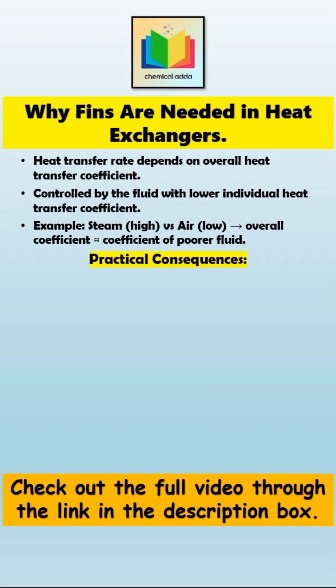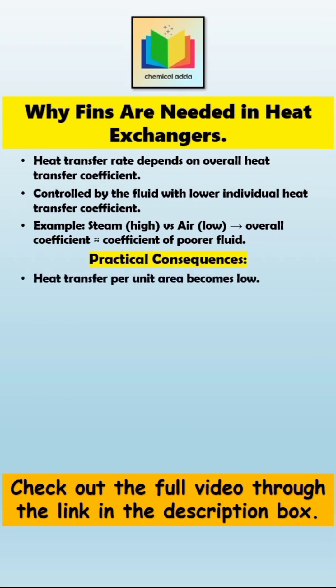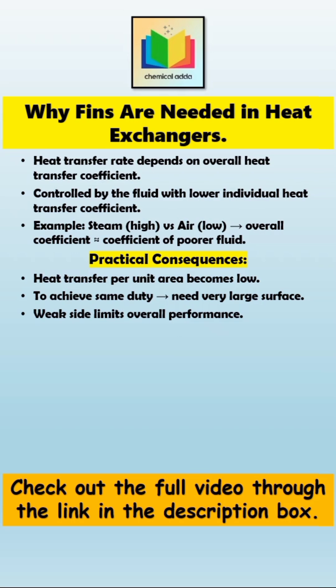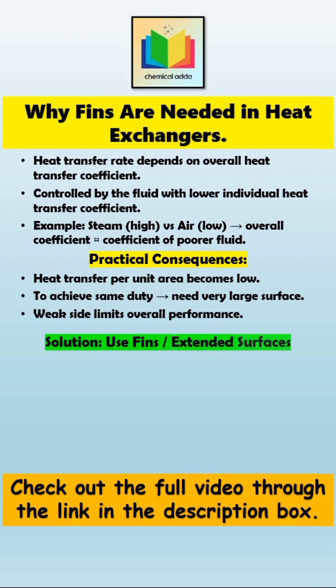The first practical consequence is that the ability of the heat exchanger to transfer heat per unit area becomes much lower. To achieve the same heat duty, the exchanger would then require a very large heat transfer surface. In other words, no matter how good one fluid is at transferring heat, the weak side limits the performance of the entire system. Therefore, to prevent the design from becoming expensive, fins or other extended surfaces are used in heat exchangers, because these fins increase the outside surface area of the tubes.